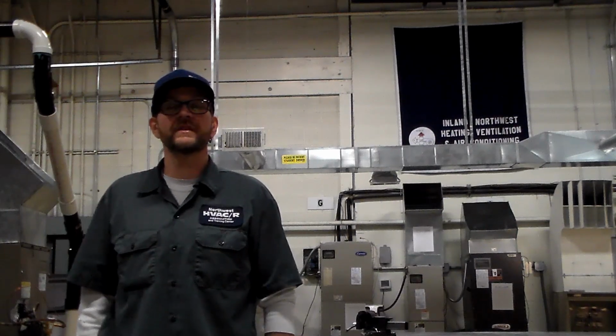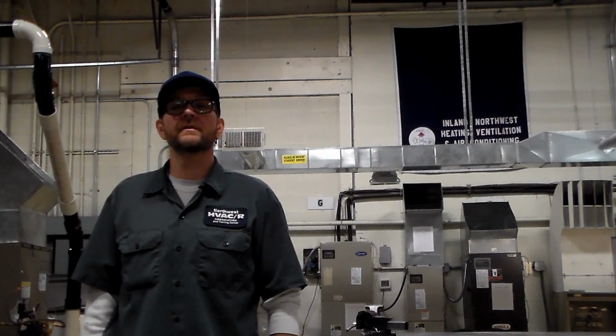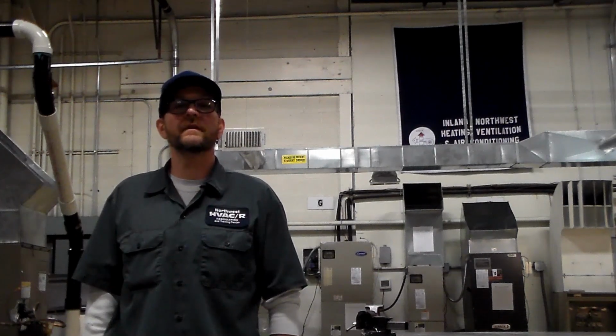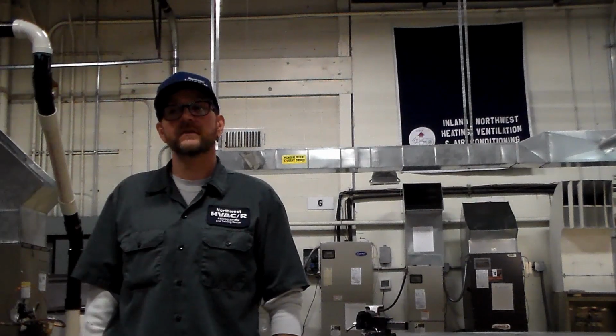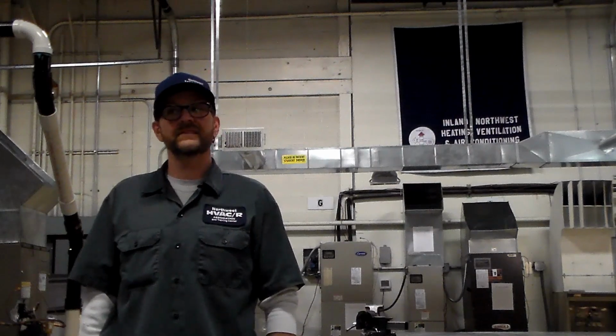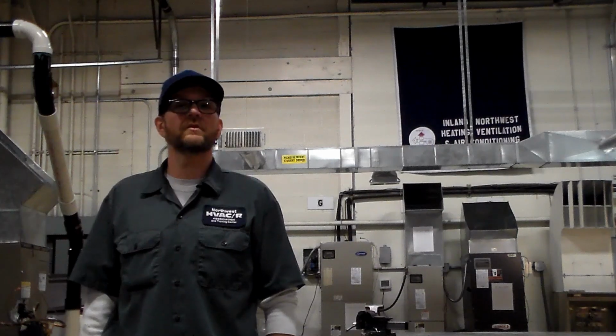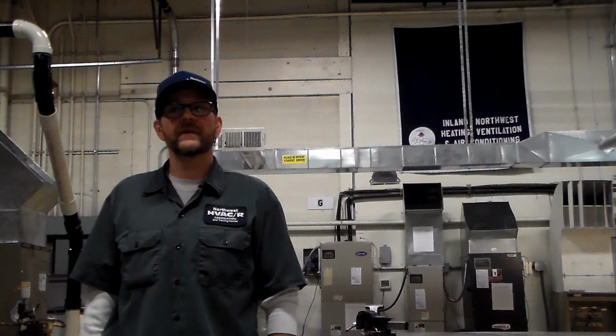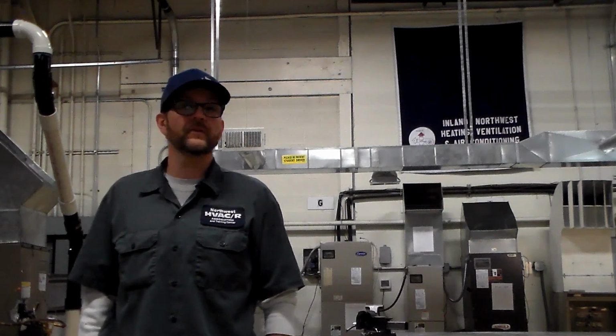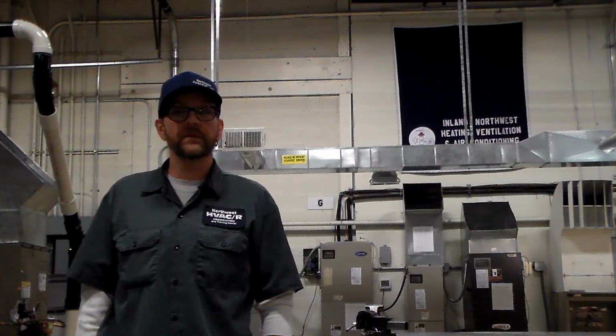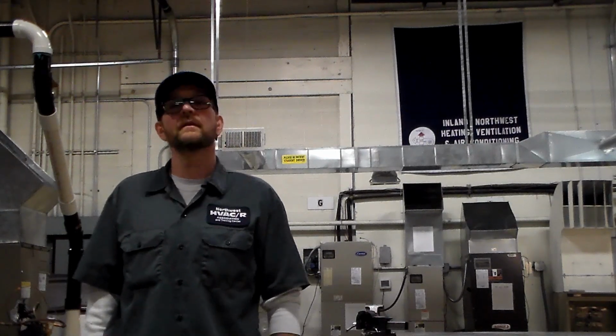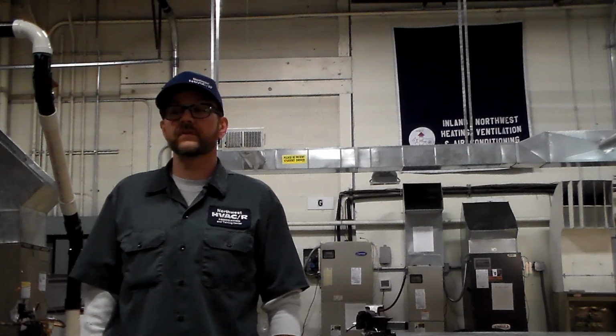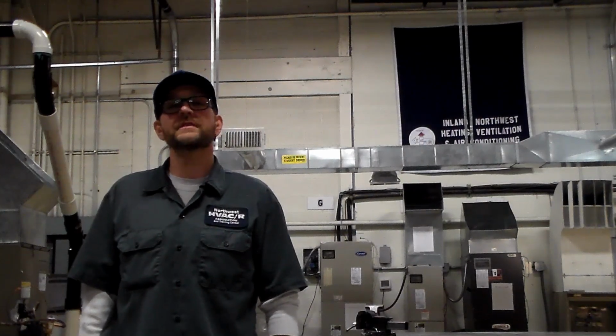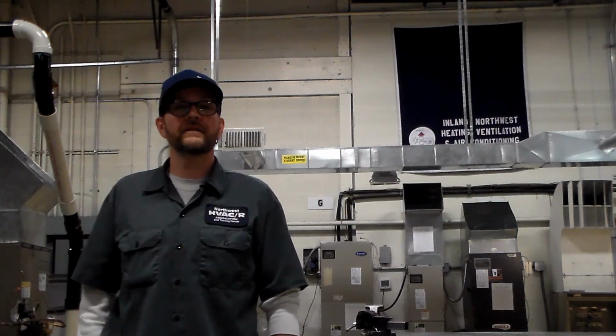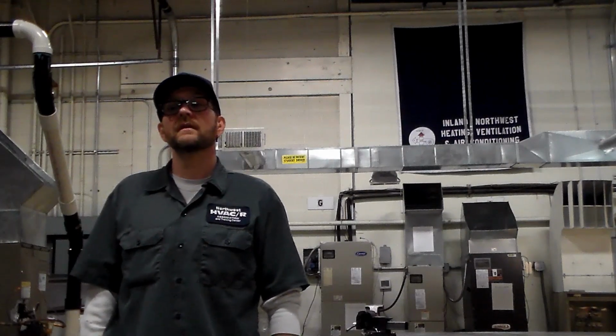I can't really go too much into the operation of a heat pump that I haven't already covered. I think it's mostly the boards and how they're wired and the things that are on them and how you test them and where they go and whatnot. That is what people struggle with. So I think the concept of reversing the refrigeration isn't necessarily a tough concept. I think it really comes down to the controls, because your standard AC, it doesn't have a board. It's very simple. Y from the thermostat energizes the contactor, it pulls in, the thing runs. Defrost is a little more complicated. It's got sensors attached to it. It controls the outdoor fan. It's got that reversing valve thing going on. So it's got various different components that are wired back to the board. But if you understand those components, the terminology on the board, and the basic function of what that board is supposed to do in the heat pump, it's actually really not that difficult.